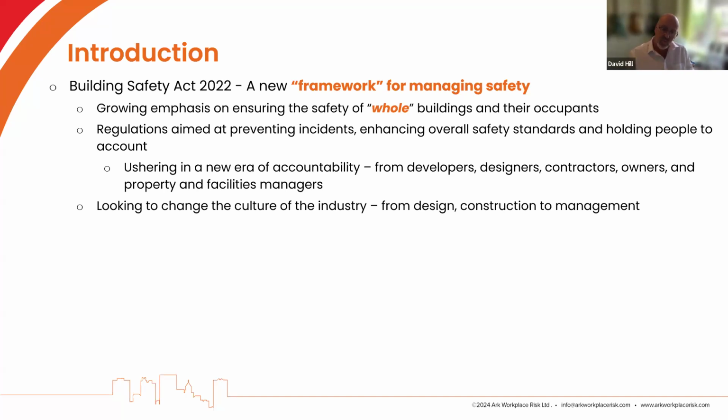There's a growing emphasis as well to look at buildings as a whole system. That is, again, very important because the vast majority of people who undertake fire risk assessments tend to focus on the areas that they have control in. Invariably, that's going to include the common areas only. I think the difficulty we have is that if you were to take the number of fires that have occurred in just blocks of flats over the last 2 or 3 years, 90% of them don't have an impact or actually start within the common areas. They are in the tenants' and residents' demised areas. And yet most people undertake risk assessments that focus away from that.